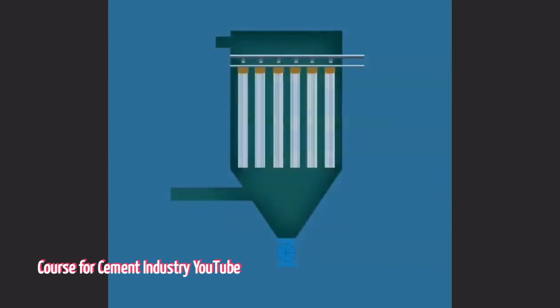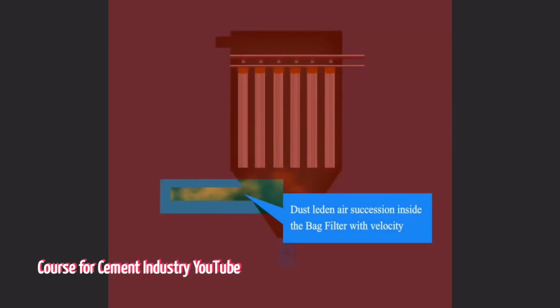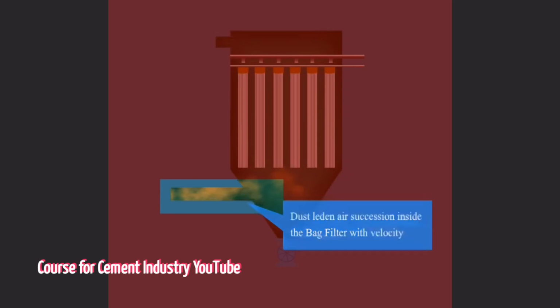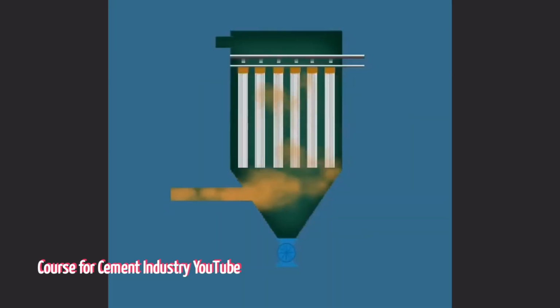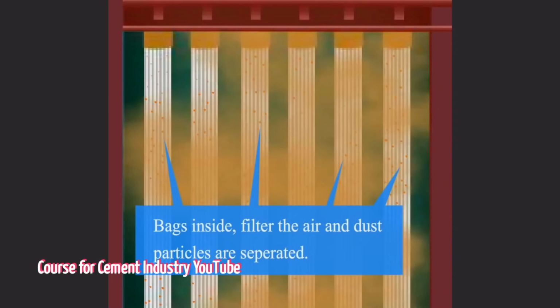So if we zoom out again, you have to picture this happening constantly. Filtration is ongoing, the dust cake is building up, the pressure drop is being monitored, and then triggered by that pressure drop, sections of bags get pulsed, cleaned, the dust falls, and they go right back to filtering efficiently. It's a continuous cycle.